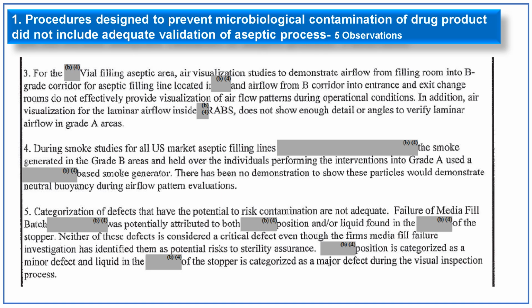The fourth point: during smoke studies for the US market aseptic filling lines, the smoke generated in the grade B areas and held over the individuals performing interventions into the grade A used a specific smoke generator. So there has been no demonstration to show that these particles would demonstrate a neutral buoyancy during airflow pattern evaluations.